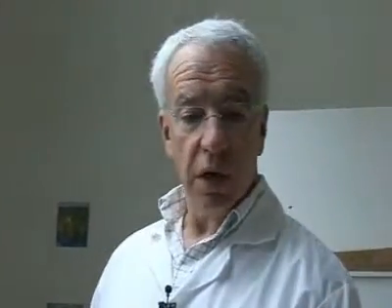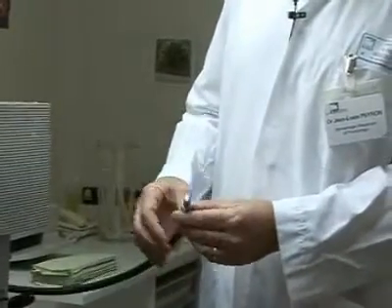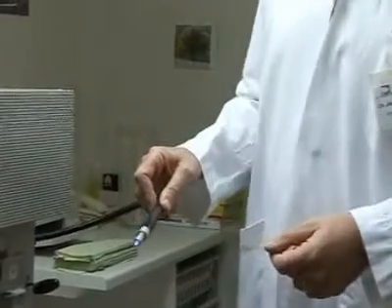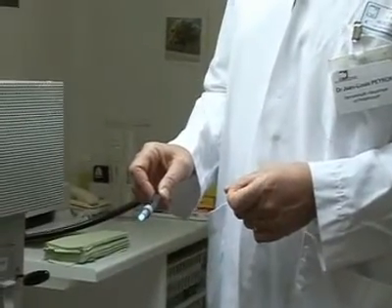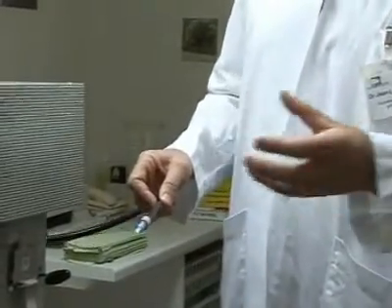We will determine whether it's ultraviolet A rays, ultraviolet B rays, visible rays, and so on. To do this, the device we are using is equipped with a monochromator, which enables light to be cut into slices, as it were. In this case, we are going to make slices of UV-A and then slices of UV-B. The light comes out of this fiber optic — we can see the light coming out here, the ultraviolet A rays from this small fiber. It will be applied to the patient's skin for a very short period of time at a dose we will define at the beginning, and we will see the appearance or non-appearance of the eruption according to whether the patient is sensitive to that wavelength.